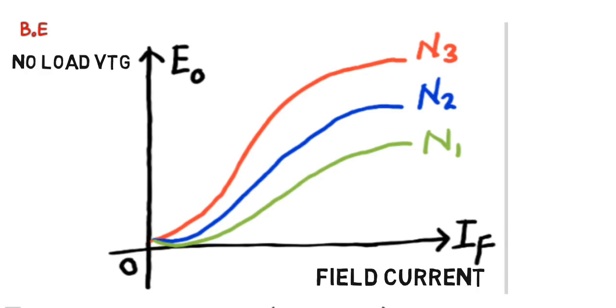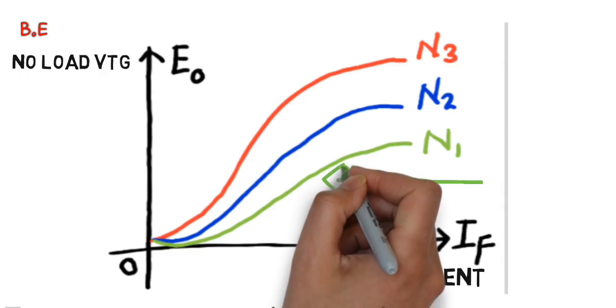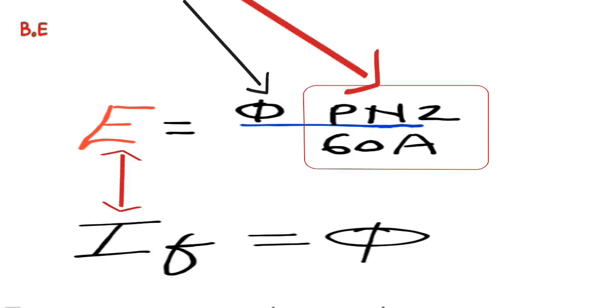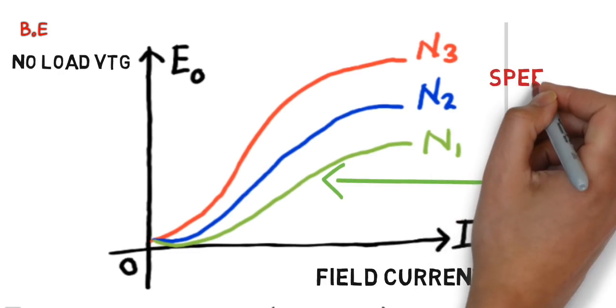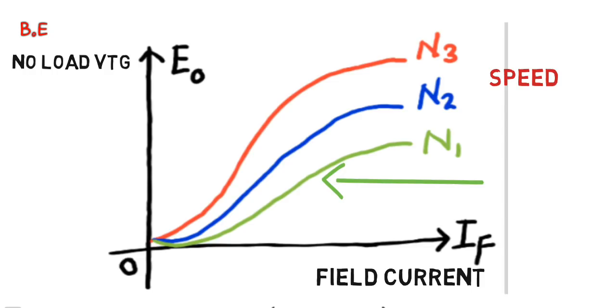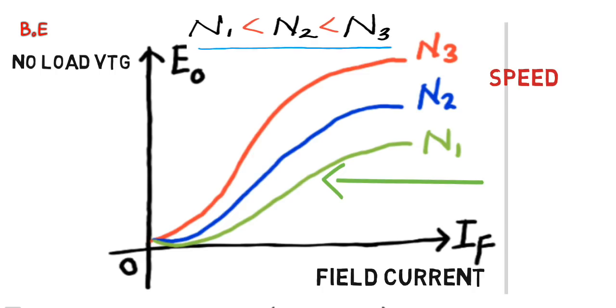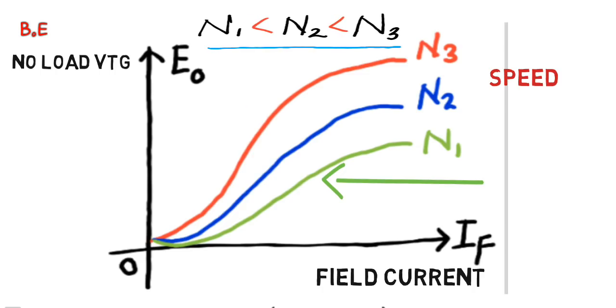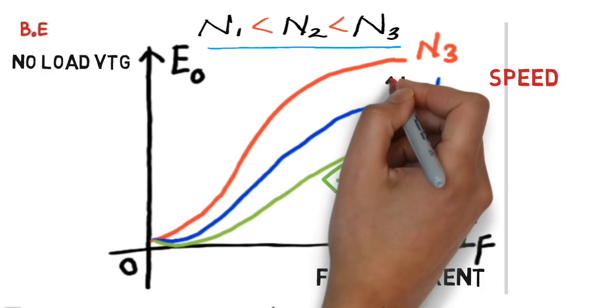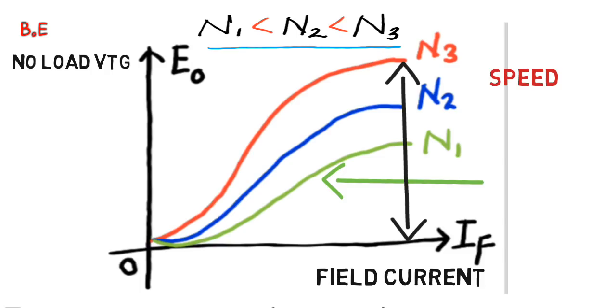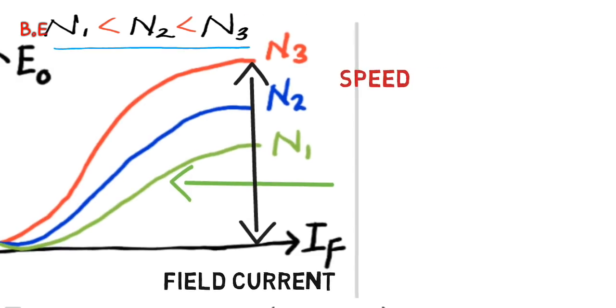Increasing field excitation increases induced voltage. Since induced voltage also depends on speed, we draw characteristics for different speeds — increasing speed also increases induced voltage, so induced voltage for N3 is greater than for N1. However, after a certain field excitation, the core gets saturated and flux becomes constant, so voltage also remains constant after that point. This is the open circuit characteristic.